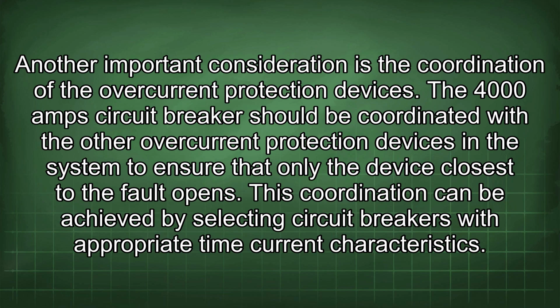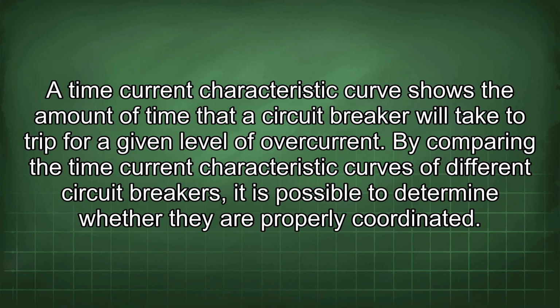Another important consideration is the coordination of the overcurrent protection devices. The 4000 amp circuit breaker should be coordinated with the other overcurrent protection devices in the system to ensure that only the device closest to the fault opens. This coordination can be achieved by selecting circuit breakers with appropriate time current characteristics. A time current characteristic curve shows the amount of time that a circuit breaker will take to trip for a given level of overcurrent. By comparing the time current characteristic curves of different circuit breakers, it is possible to determine whether they are properly coordinated.